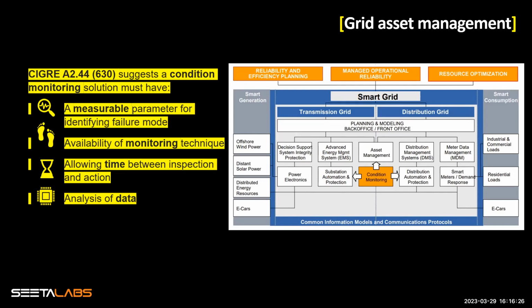You have to have a parameter which is easy to identify, which can be measured and monitored. Every time you monitor or measure that parameter, you must have enough time between inspection and action, by interpreting the result, the course of action that follows, or whatever consequence follows because of that parameter. Case in point, those of you who work on the high voltage side of things, or are familiar with transformer insulation degradation, must have heard of something called dissolved gas analysis.